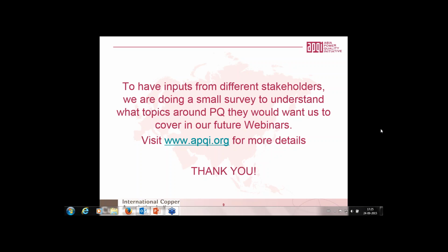The question is from one of the attendees, who mentions that in Tamil Nadu there is an enforcement of limitation for harmonics, and the meter specification says that the total kilowatt hour should be the sum of fundamental power plus harmonic power. Now, the active power is carried by fundamental voltage and current, and all harmonic power is reactive power. Can you please clarify?